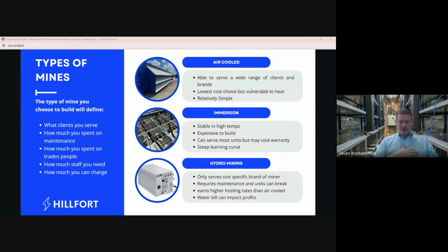None of the units we had were built for immersion. So we had to literally go in, retrofit every single air-cooled machine, convert it to being an immersion unit, test it because we had to make sure it worked after the conversion, and then dunk the units. Per machine, that process took about an hour. So mentally, just imagine you have a megawatt of immersion, which is about 250 units, assuming you overclock to 4,000 watts. You're talking about 250 hours of just preparation and dunking time, minimum.